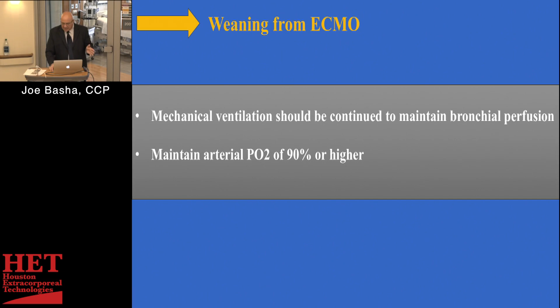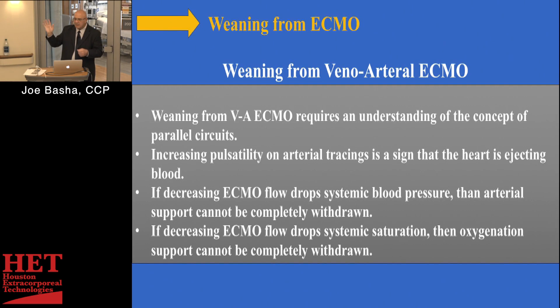If it's VA, it's going to be a completely different situation. Remember what I told you: if you start turning the flow down, which you're going to have to do in VA, you've got to make sure they're oxygenated. As you turn that flow down and the heart starts to eject, those lungs need to be working, because otherwise you're going to have the problem I discussed earlier of parallel circuits in essence. To do VA, you have to turn the flow down, which means you've got to make sure the patient is appropriately anticoagulated so you don't have the flow going so low that there's such a long transit time that you start creating little clots that you just keep pumping into the patient. They may not stay in the circuit and clot the circuits, you may literally be pumping them into the patient. So you've got to be careful and cognizant of that.